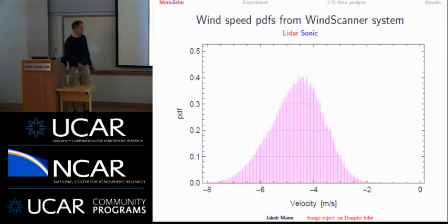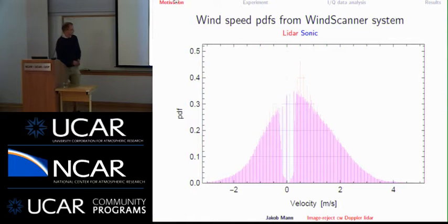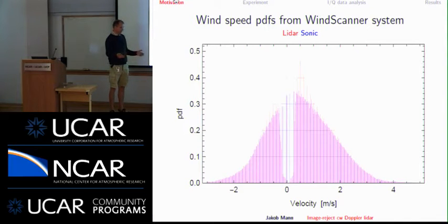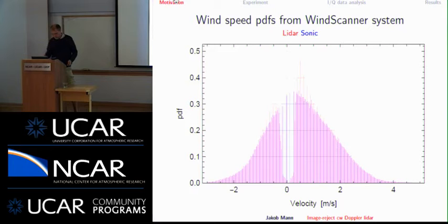Then you take another path and take the same hour of data and look at what happens there. Now the sonic has a nice PDF here, but the lidar cannot measure close to zero with the AOM. There's too much noise around zero for us to always extract the velocity. It depends, of course, on the measurement volume. The larger the volume, the wider the Doppler peaks and the easier everything is. But these data are from a small measurement volume because we have focused quite close to the instrument. All right, so that's a problem.